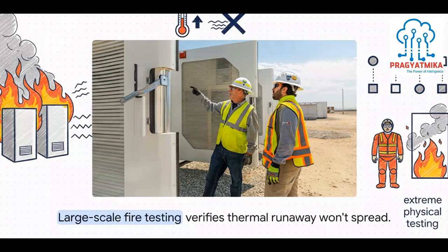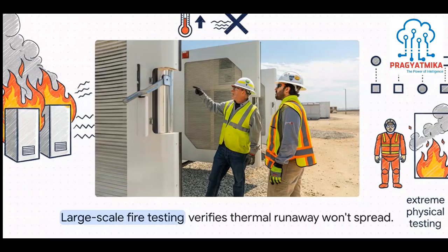Before a BESS site is even built, these systems are literally set on fire in specialized labs. They do this to absolutely verify that the complete combustion of one single enclosure won't cause a thermal runaway event in the unit sitting right next to it. It's all about precise spacing, proven through extreme physical testing.